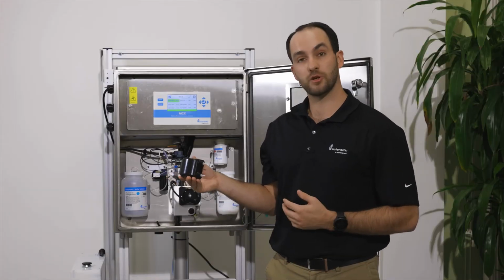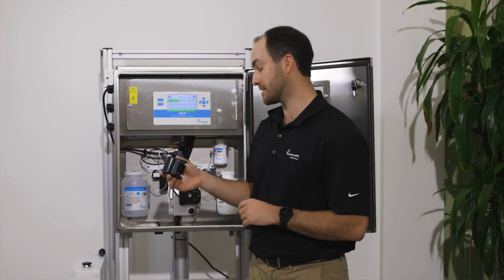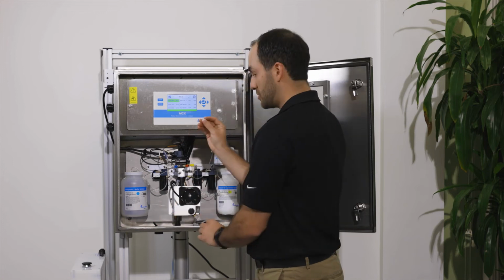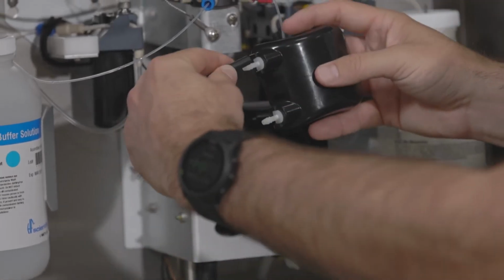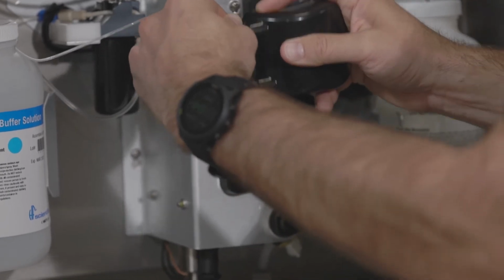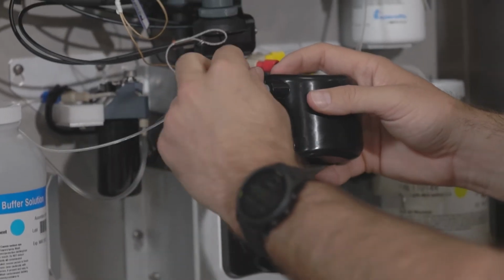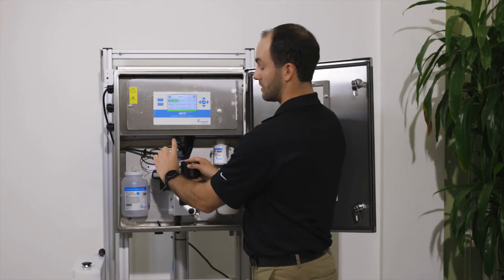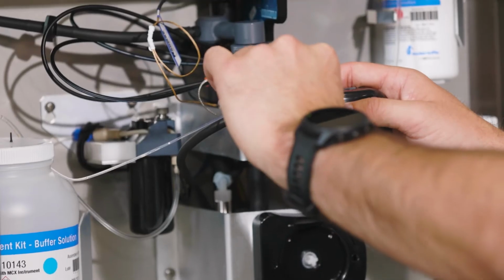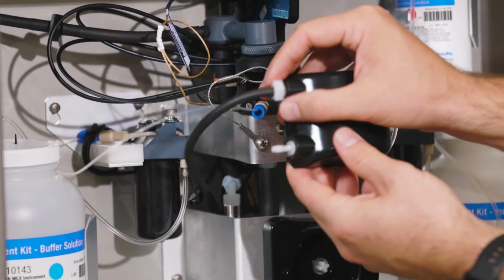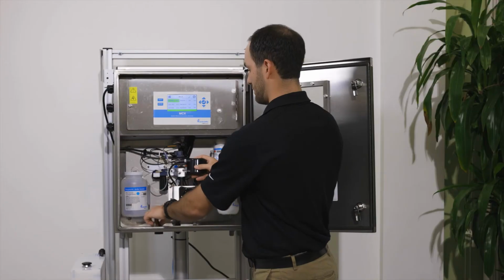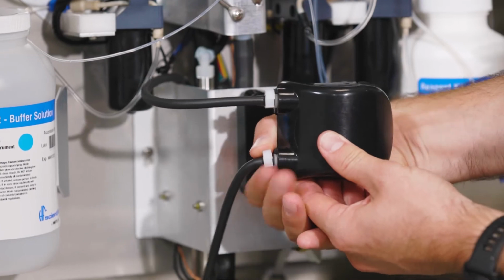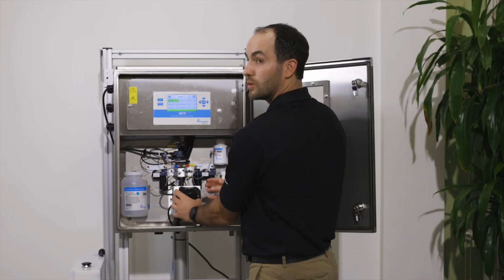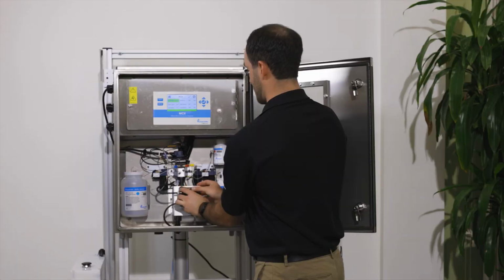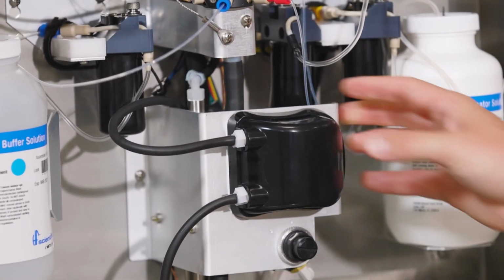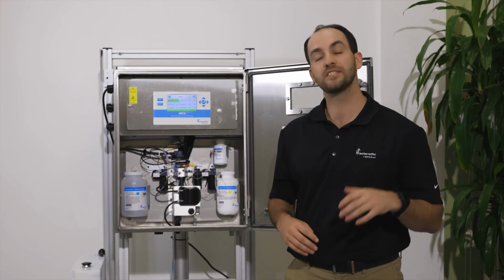Once you're ready to replace your peristaltic pump, we'll start by connecting the lines. Make sure you have the two clips on each of the lines before you connect it. To put the clamp down, press on both sides until you hear a couple clicks. When you've finished, connect the pump head back on. Once you have your new pump installed, we need to prime the water pump.